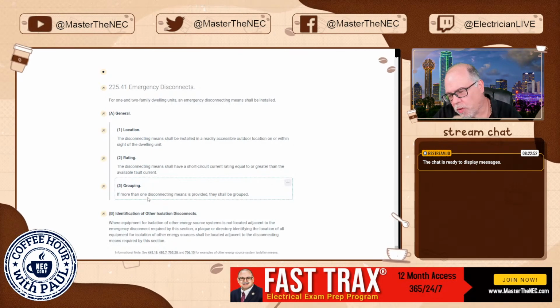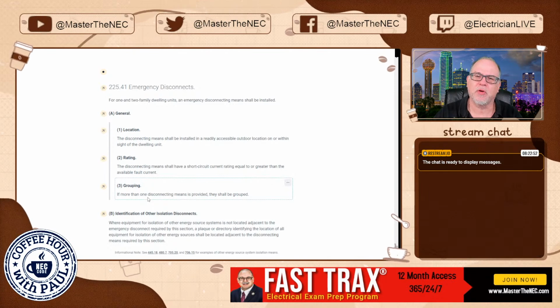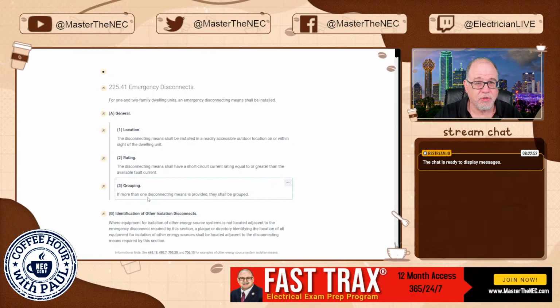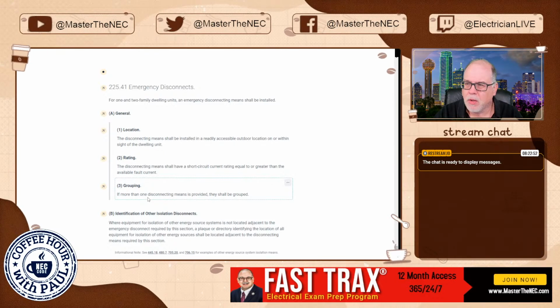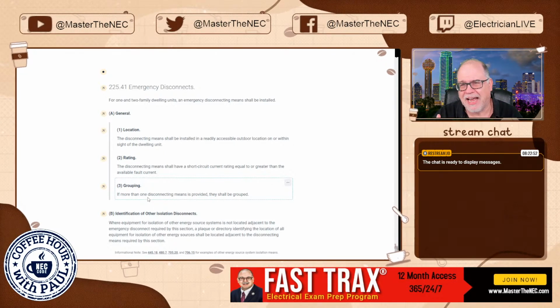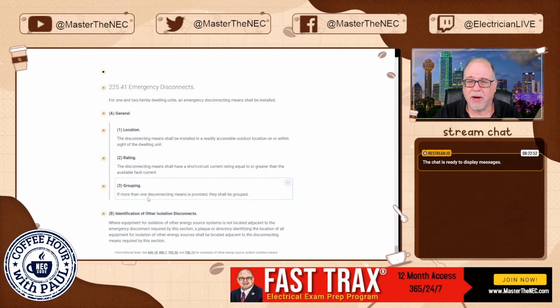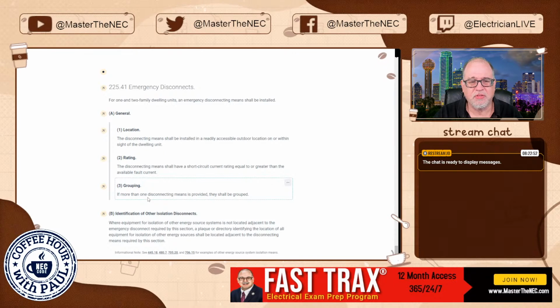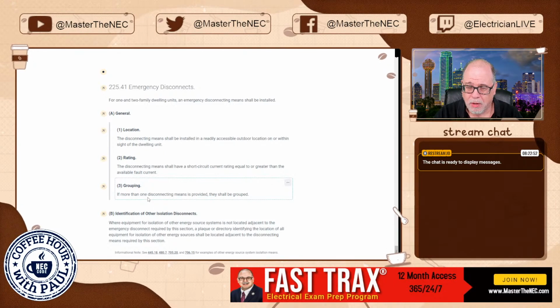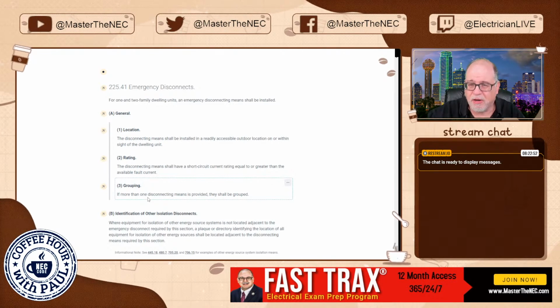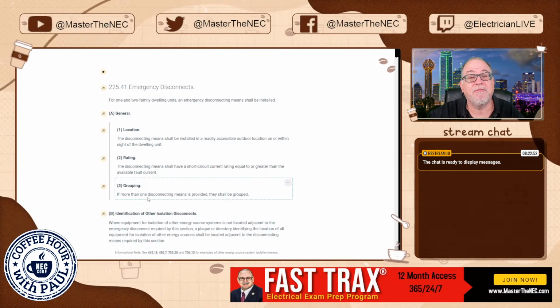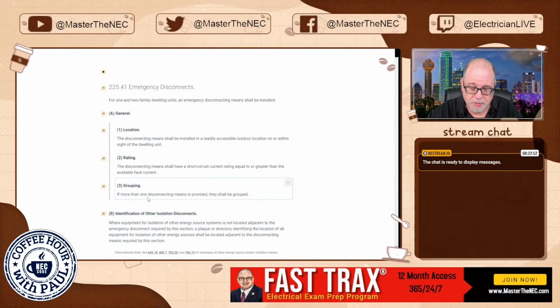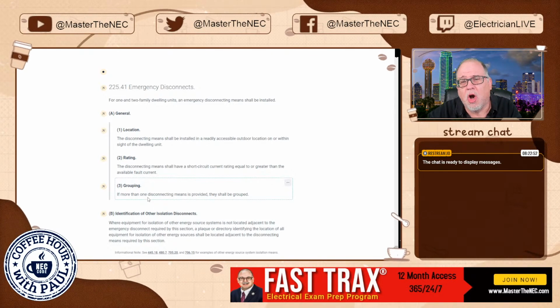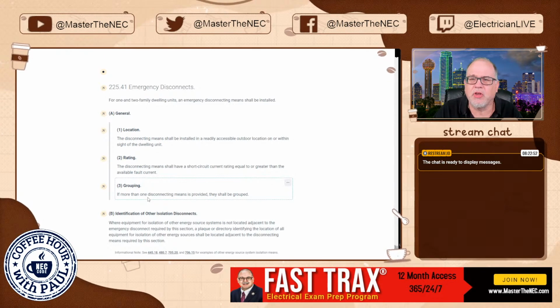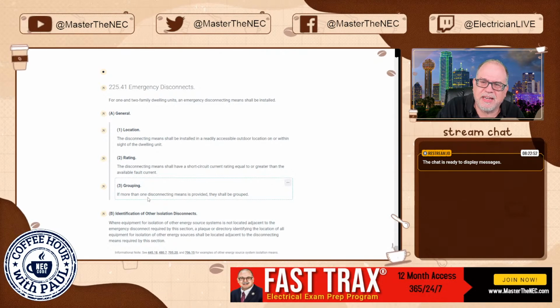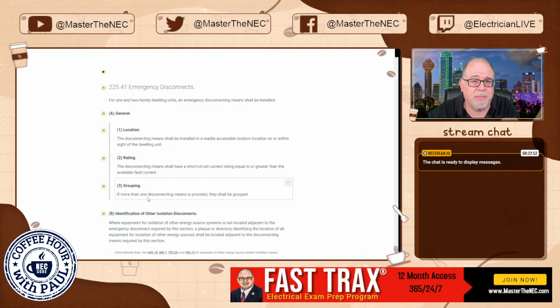Well, for the 2023 code, we're now adding this emergency disconnect to feeders that are supplying 1 and 2 family dwellings. Now, where would you have this scenario? Well, maybe you live out where your dwelling is further onto your property and the utility is stopping the service conductors at a pole. And now your electrician's taking over and you're going to be running that from that pole. You're going to be running feeders to, maybe that's your choice. You're going to put the service at the pole and now you're going to run feeder over to the 1 and 2 family dwelling. Well, now you're going to have the emergency disconnect means at that 1 and 2 family dwelling that is supplied by a feeder.